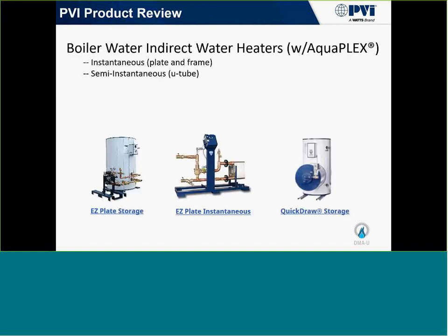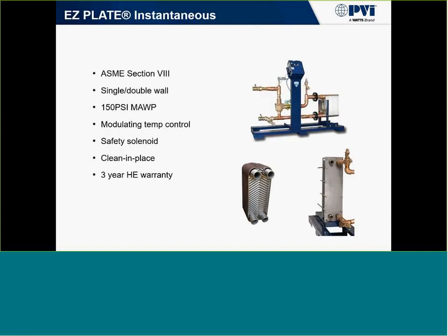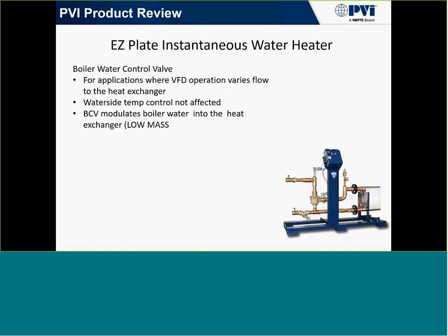And then we can also do that with boiler water. The same type of approach that we used for COBREX and COBREX storage, we can do with boiler water as well. We can do that with a brazed plate and frame heat exchanger. The same concept with upflow water, cold water coming in, upflowing, hot coming out. We can get a 5-degree approach temperature on this design, and we can clean in place just like we did with the COBREX unit.